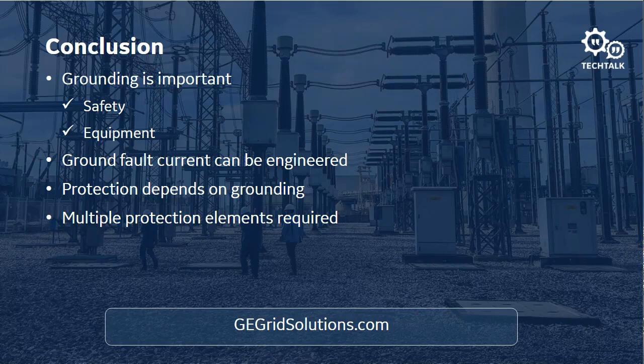Obviously, there's a lot more that we can provide in this hour that we have together. However, I hope that the seminar at least gives you an introduction into those various methodologies, not just the methodologies, but what are the advantages, disadvantages of the various ones? Why do we use the high impedance versus the low impedance? And then we talked about, once we've selected the type of grounding method for our system, how do we protect it? What are the various methods of protecting, for example, a high impedance grounded system or low impedance grounded system? Specifically, we talked about as it applies to generators.